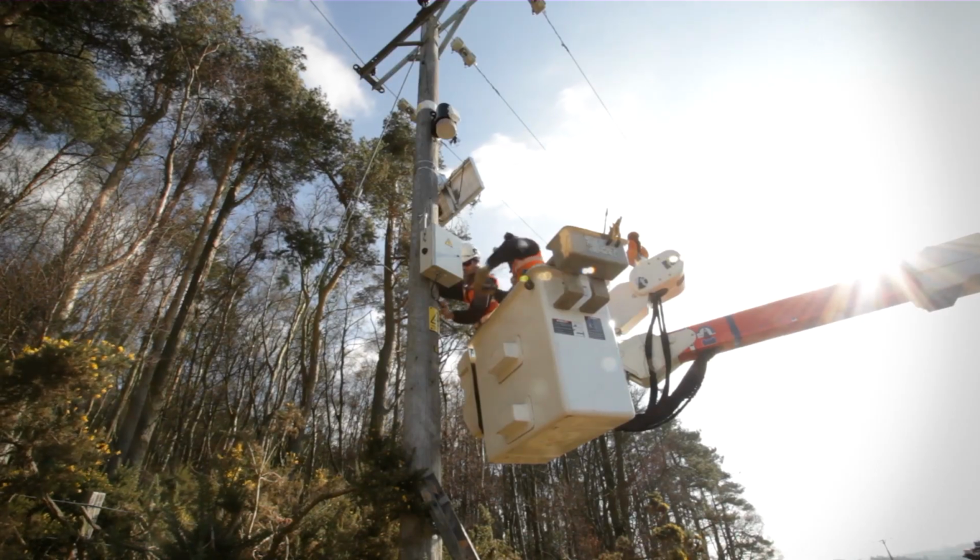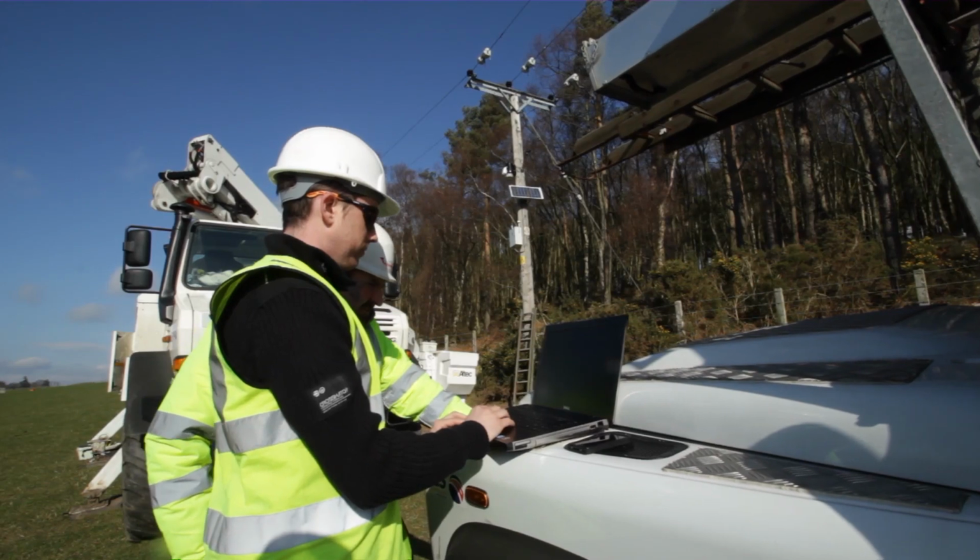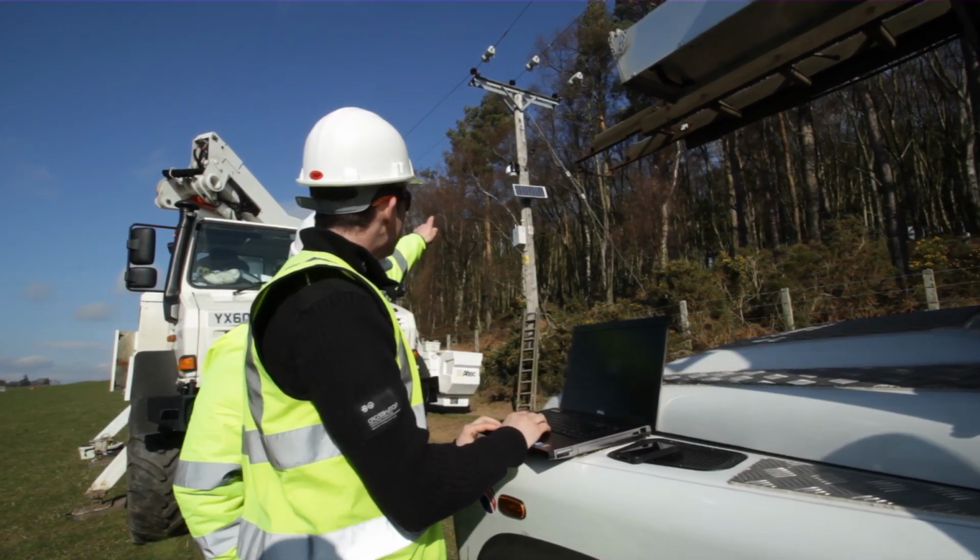We're measuring things like ambient temperature and wind speed. Those play as inputs into the algorithms and models that we have built as part of international standards. Going forward, we'll be using the RTTR data in conjunction with the GUS system. The GUS system will allow us to act on this data so that we can actuate different network interventions, for example, energy storage or demand-side response. After we switched them all on and powered them up, the lads said, oh yes, they are working, and there is some really good information coming out from them.